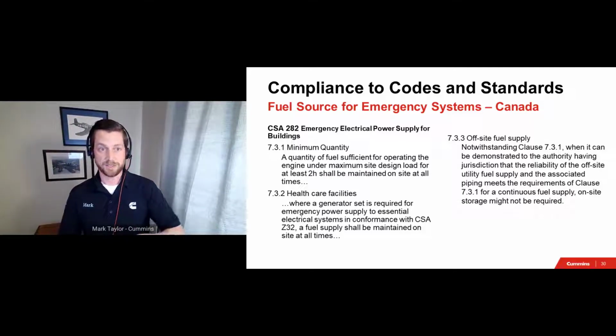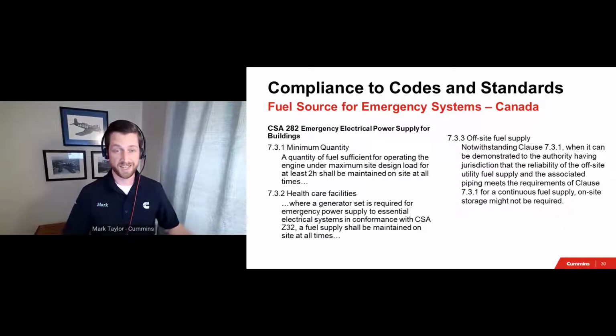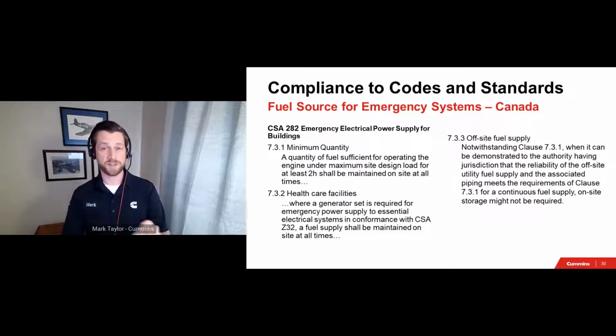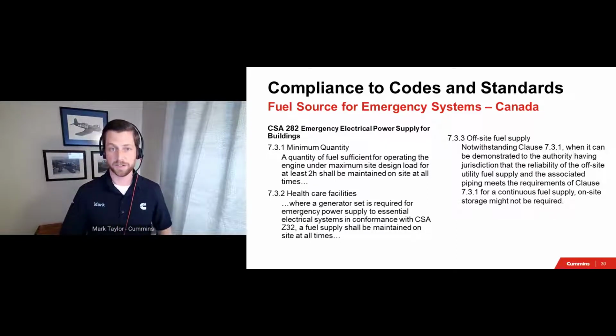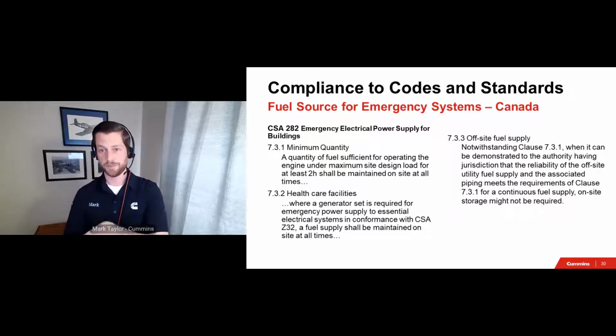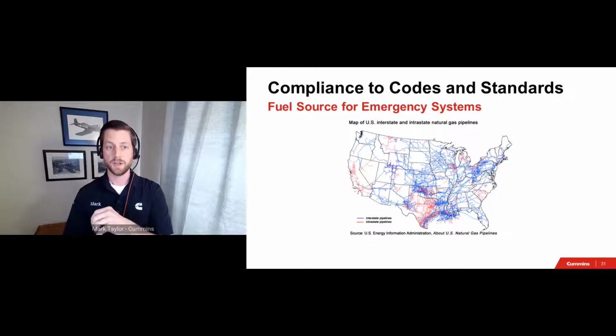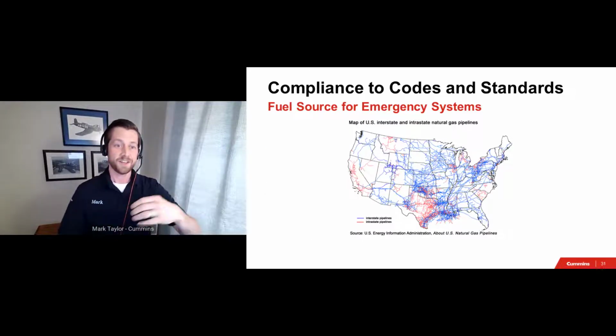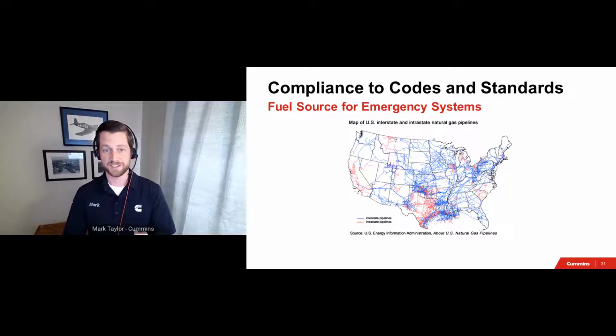Similarly to the exception clause for NFPA 110, CSA282 also provides language to deem on-site fuel storage as not required if it can be demonstrated to the AHJ that fuel supply reliability is sound. So in short, there are a lot of parallels between CSA282 for Canada and NFPA 110 for the United States. So back to the United States. Let's take a look at this map of the United States just to highlight this point more visually. Again, the driver of such a reliable source of fuel is that the infrastructure network and production sites are geographically dispersed and well interconnected.